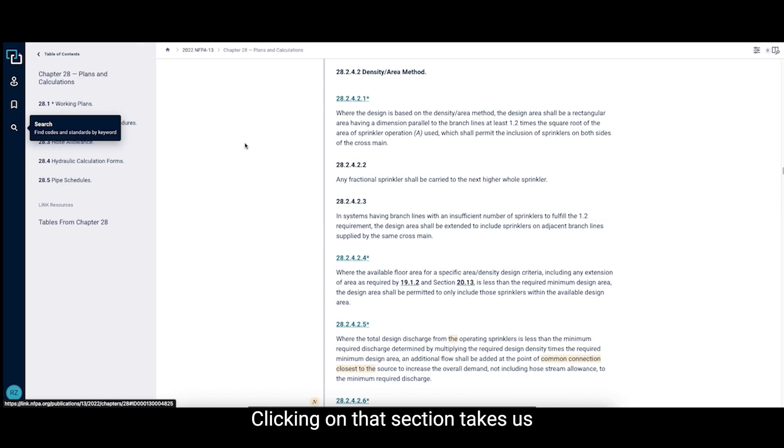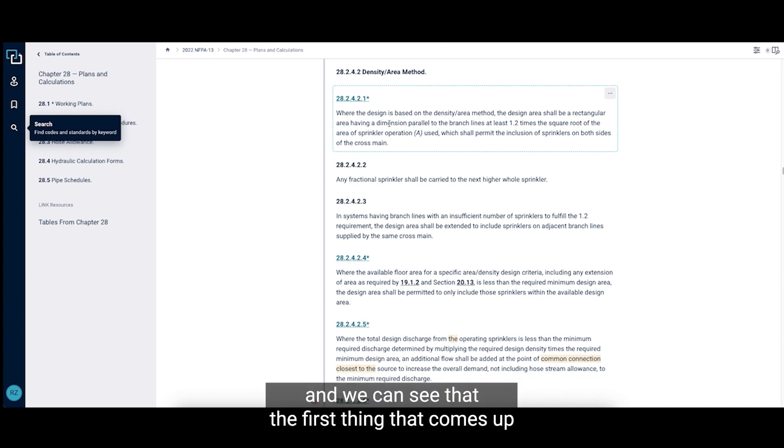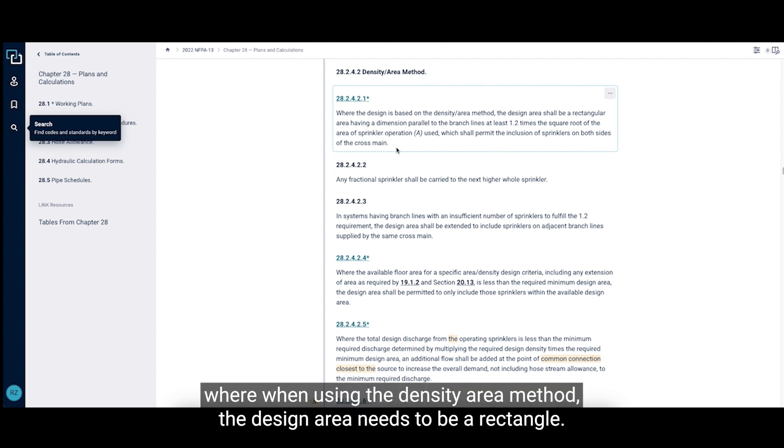Clicking on that section takes us to that portion in the code and we can see that the first thing that comes up talks about the design area, where when using the density area method, the design area needs to be a rectangle.